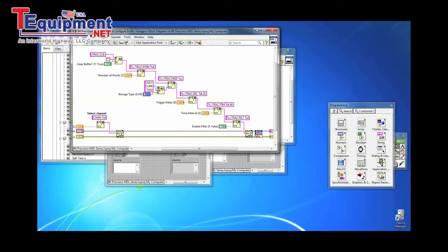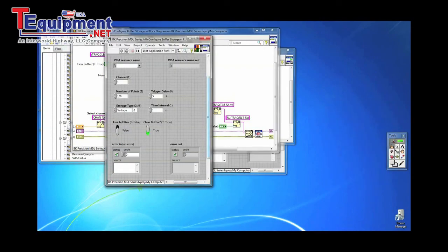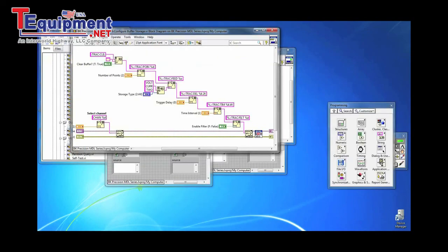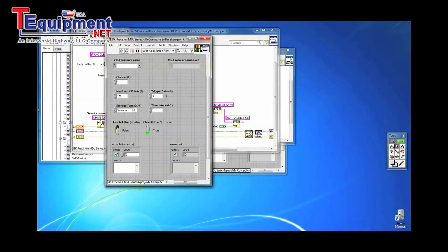You can control how quickly subsequent readings get stored into the buffer by specifying the storage operation time interval with TRAC:TIM command. You can set it to as fast as 0.2 milliseconds or as slow as 3,600 seconds. The main advantage of using buffer storage operation over data logging via PC remote control is speed. But for the purpose of showing you the effects of the interval time, I will send TRAC:TIM 1 to set the interval to 1 second between each reading.